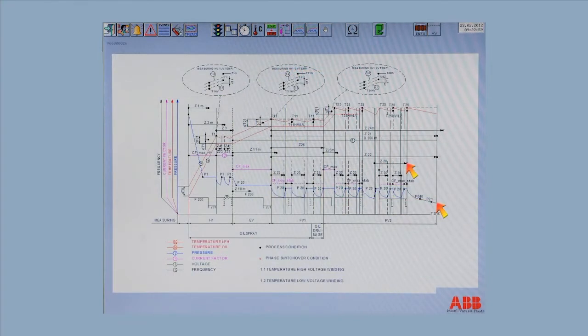The vacuum continues to increase, and when the pressure has fallen below the value specified by P21, the timer Z20 has elapsed, and the specific water extraction level has been reached in subsequent readings, then the process has achieved its objectives, and the operator can press the off button, which will lead to the manual aeration of the transformer.